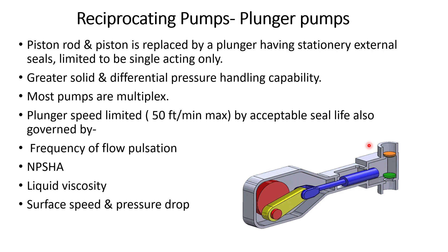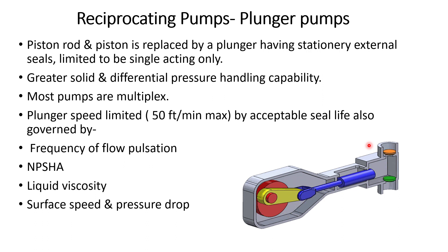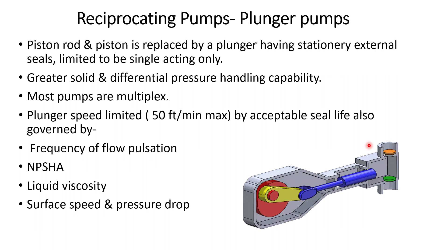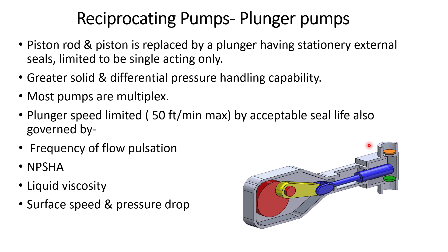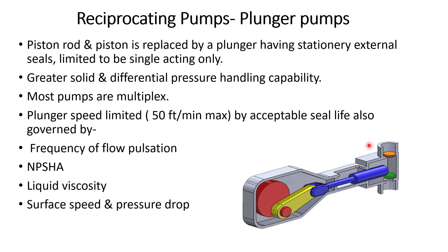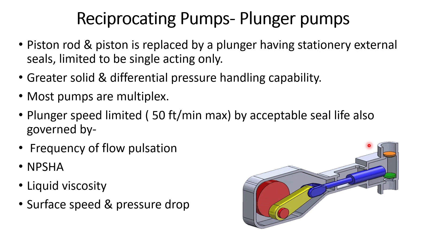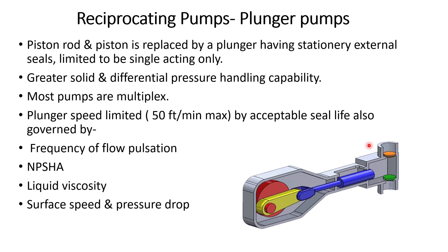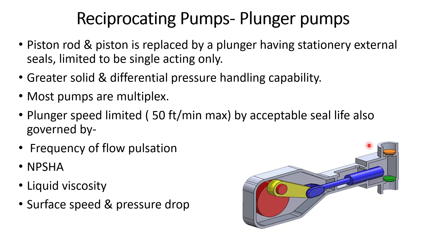Now let us talk about plunger pumps. In a plunger pump, the piston is replaced by a solid plunger with a stationary seal. Plunger pumps can only be single acting — they cannot be double acting. They can handle greater solids and the differential pressure — the difference between suction and discharge pressure — is much more than a piston pump. Most of these plunger pumps are multiplex, meaning there are multiple pumps operating from the same crankshaft.